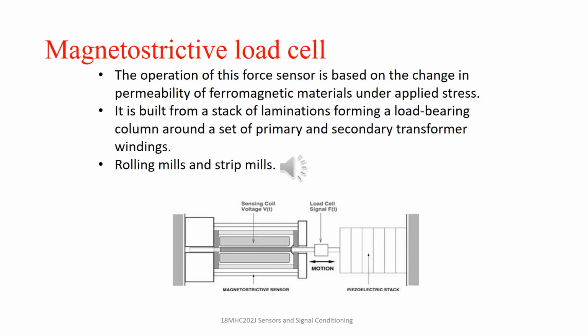The operation of this force sensor is based on the change in permeability. It is built from a stack of laminations forming a load-bearing column around a set of primary and secondary transformer windings. When the force is applied, the stresses cause distortions in the flux pattern, generating an output signal proportional to the applied load. This is used for force and weight measurement in rolling mills and strip mills.